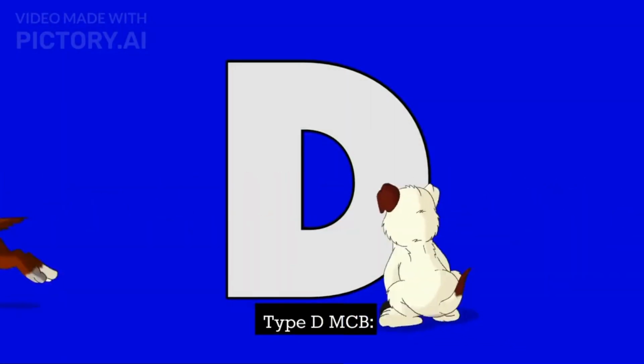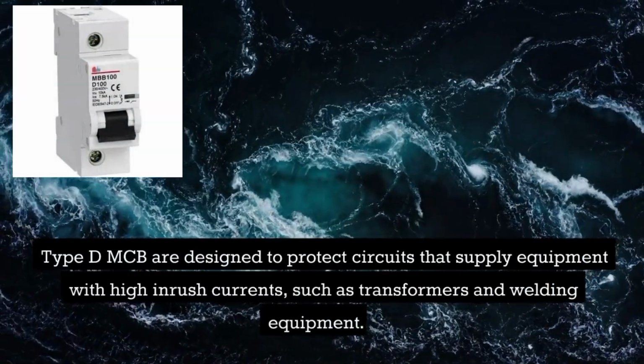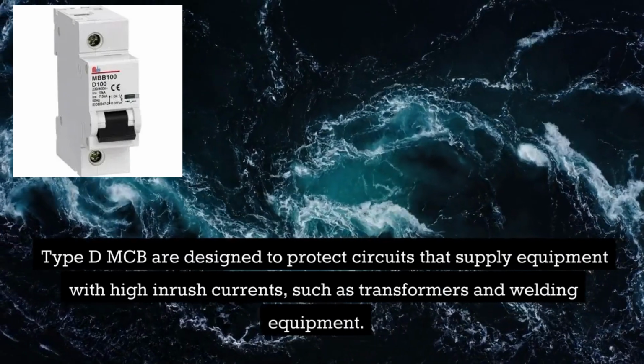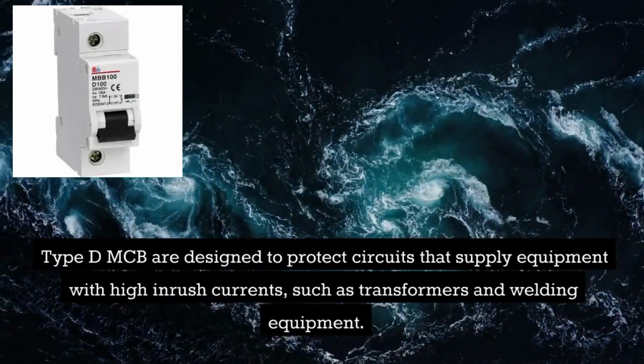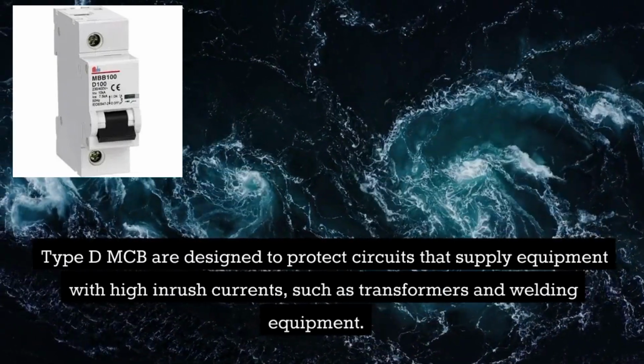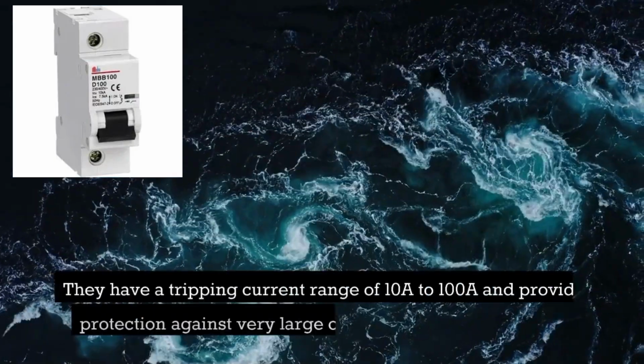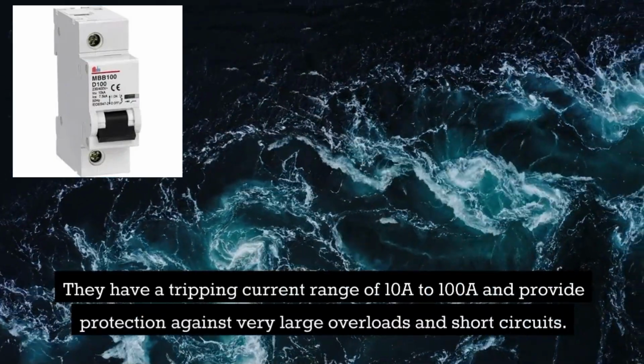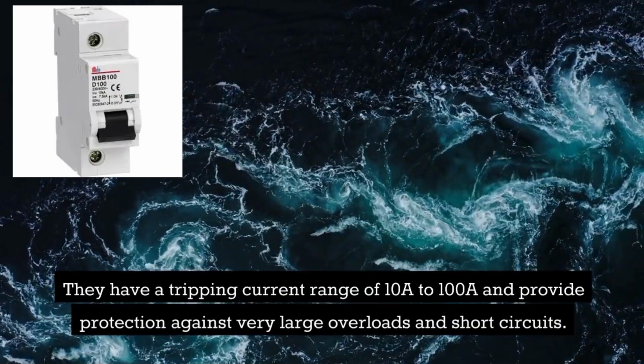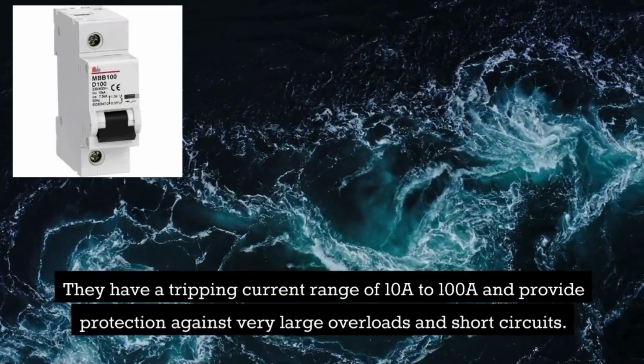Type D MCB. Type D MCB are designed to protect circuits that supply equipment with high inrush currents, such as transformers and welding equipment. They have a tripping current range of 10A to 100A and provide protection against very large overloads and short circuits.